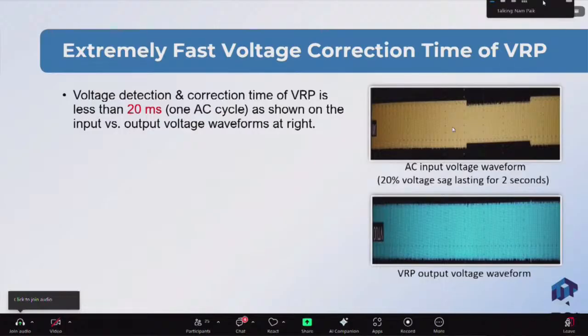You can see the 20 millisecond dip is hardly visible in that two-second window. But in another diagram, you'll see a small 20% drop on that one cycle for 20 milliseconds, and then the next AC cycle shows the correct voltage that the VRP has worked to produce.